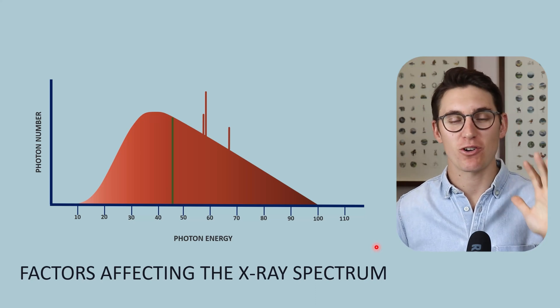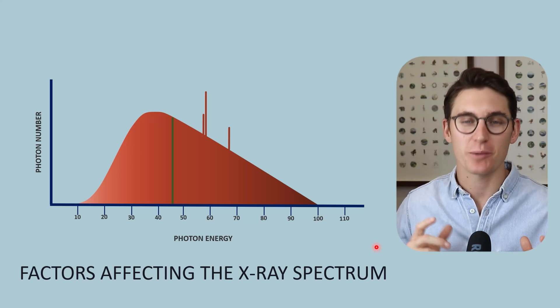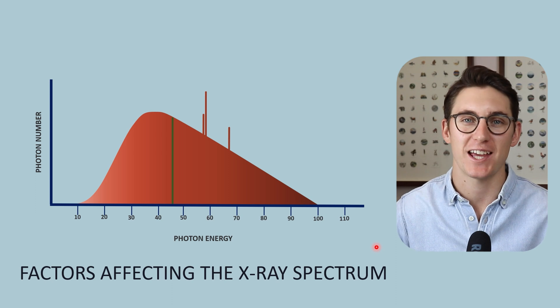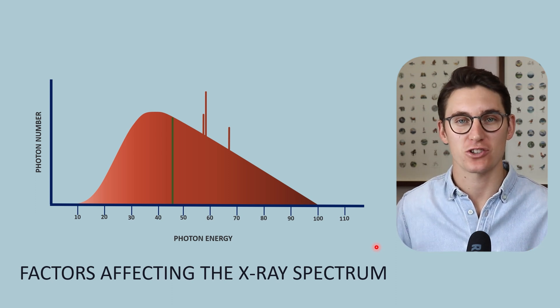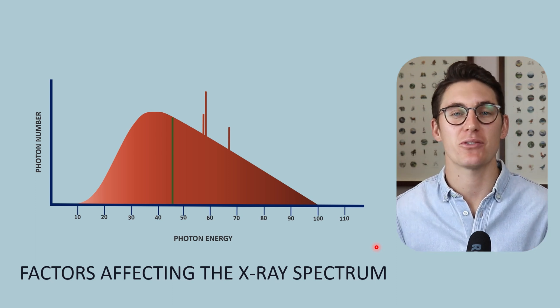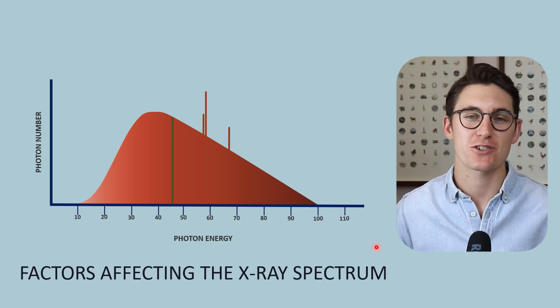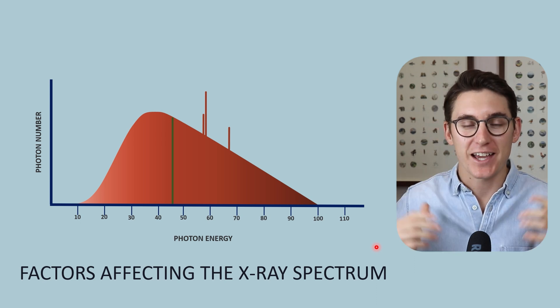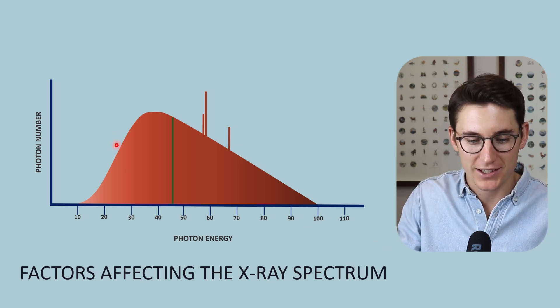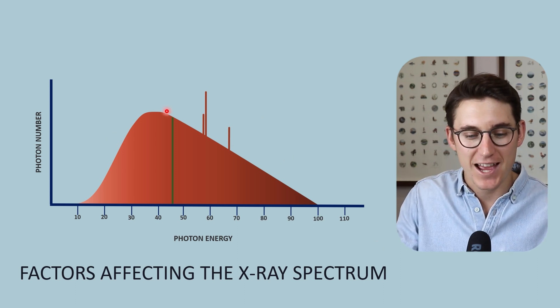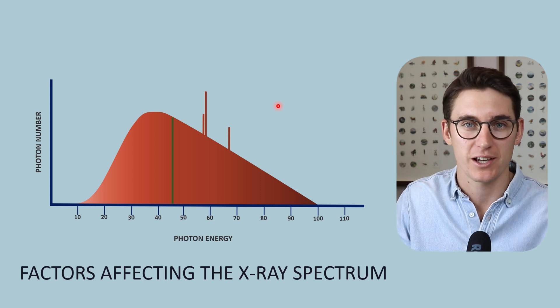In the last talk I mentioned that there are five main factors that we can manipulate in order to change the x-ray spectrum. Changing those five factors will either have an effect on our x-ray beam quantity or our x-ray beam quality. The x-ray beam quantity is represented by the red here — the area under the graph, the number of photons within our x-ray beam.